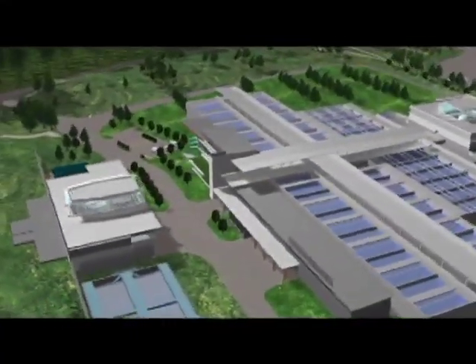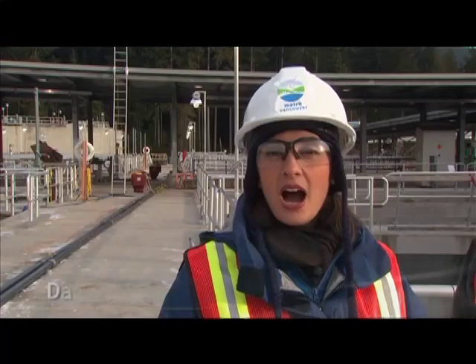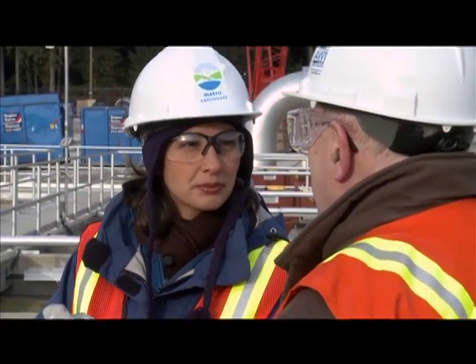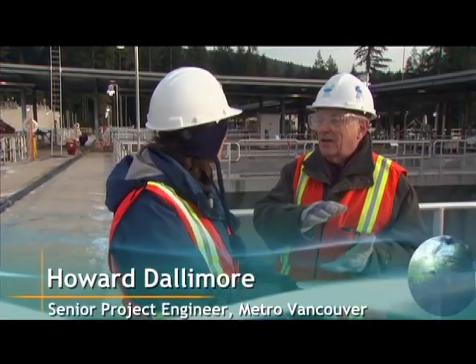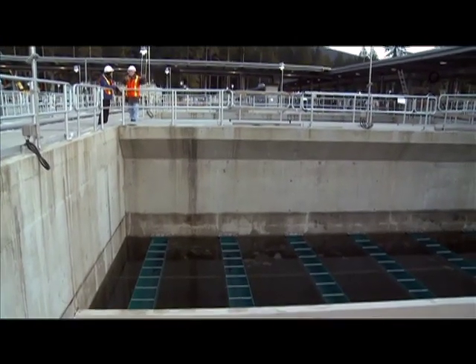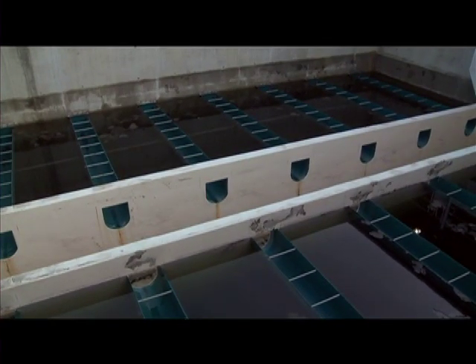This new facility will eliminate turbidity, reduce chlorine requirements, and ensure the water meets Canadian drinking water quality standards. I'm here above the 24 tanks where water will be filtered. Howard Dallimore is part of the project management team overseeing construction. Can you tell me a little bit about what's going on in the tanks? This is a filter tank, and right at the bottom of it is about 300 millimetres of sand, and above the sand is 1.7 metres of anthracite. Anthracite is a type of very hard coal. Water moves slowly down through the filter, and as it does, any particles in the water, such as silt, organic matter, bacteria, and viruses, are trapped in the filter bed.